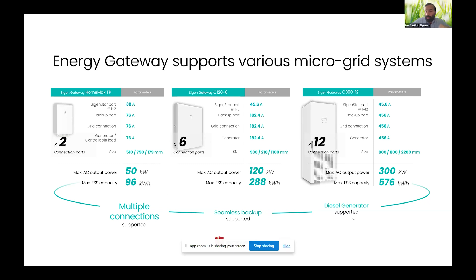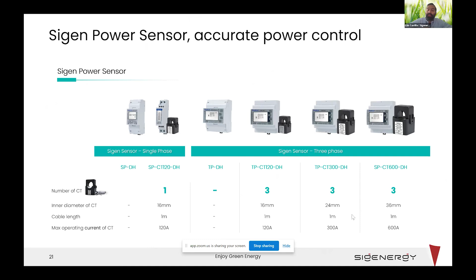Another piece of equipment is the Sigen power sensor. This is a Modbus meter with HCTs. We have a single phase version that's up to 120 amps, and for 3 phase we have 3 versions: 120, 300, and 600 amps. This is just a simple Modbus meter. It comes with the CTs, and it needs to be hardwired to the energy controller.